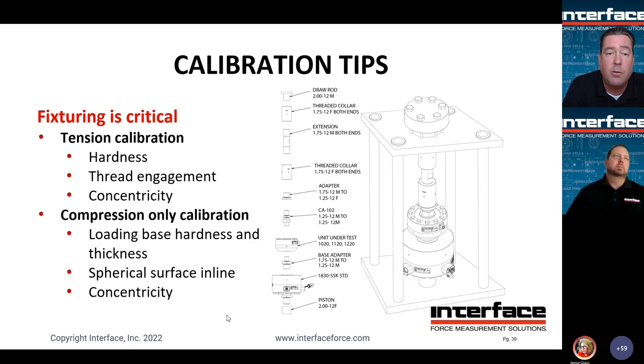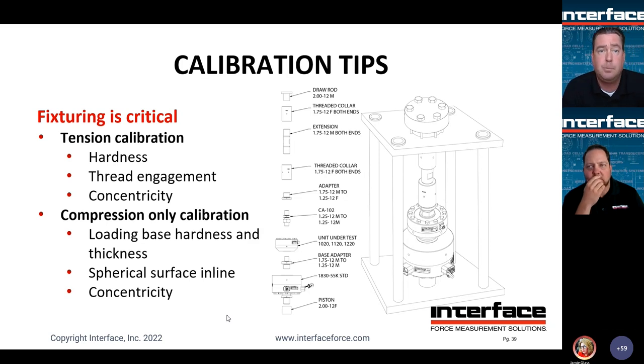Compression only considerations, making sure that the loading base hardness and thickness is sufficient to not deflect appreciably under the calibration load. Making sure that there's a single point of contact somewhere in that load string to make sure that there's not any undue misalignment error. And again, concentricity also comes into play there as well, making sure that that applied force is as concentric as possible. Again, any off-axis or misalignment is going to manifest at some level as an error in the calibration. Next slide, please.